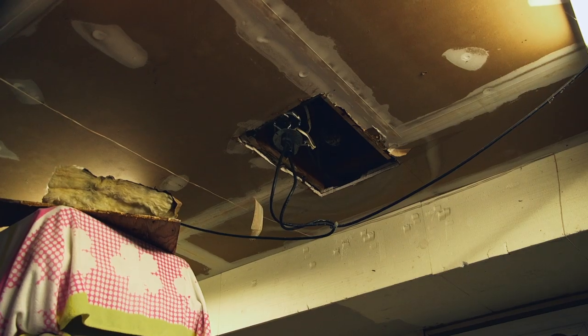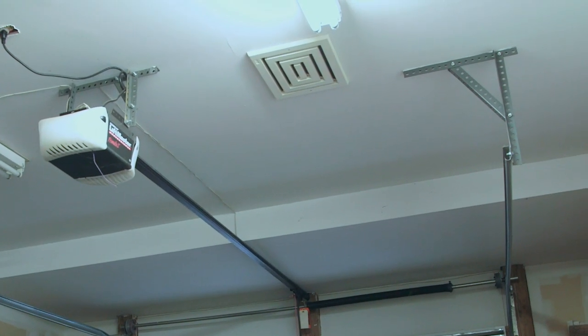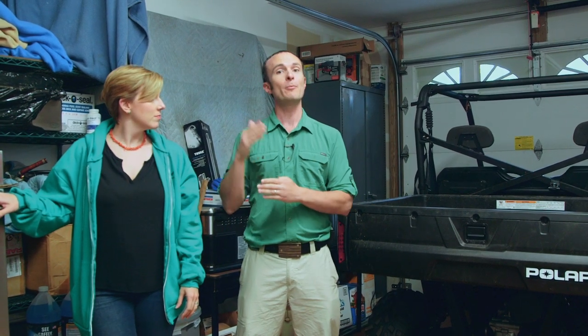Right now, you can see that there are some obvious air leakage pathways between the house and the garage. We're going to test all that stuff. Really, really critical. And there's a whole second garage. So we have an exhaust fan, which is interesting. They installed it because there were fuel burning appliances. So we're gonna want to absolutely know what's going on in here so that we can help our homeowner move forward. One of the easiest ways to take out contaminants from your home is with a fan.